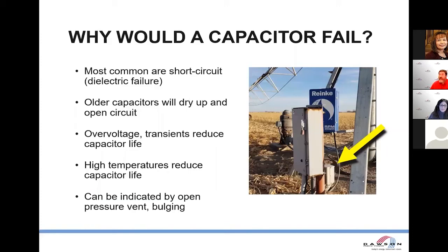High temperature can reduce capacitor life. So obviously, welcome to Nebraska. It gets a little warm in the summer, so those capacitors probably are experiencing some high temperatures, which would reduce their life. If you go to your capacitor and open the little container that it comes in, you'll see, in the picture here, the yellow arrow points at the box which holds the capacitor on this particular service. And you see that the capacitor is bulging or it has an open pressure vent. That's a good indicator that that capacitor has failed and it's no longer doing its job.